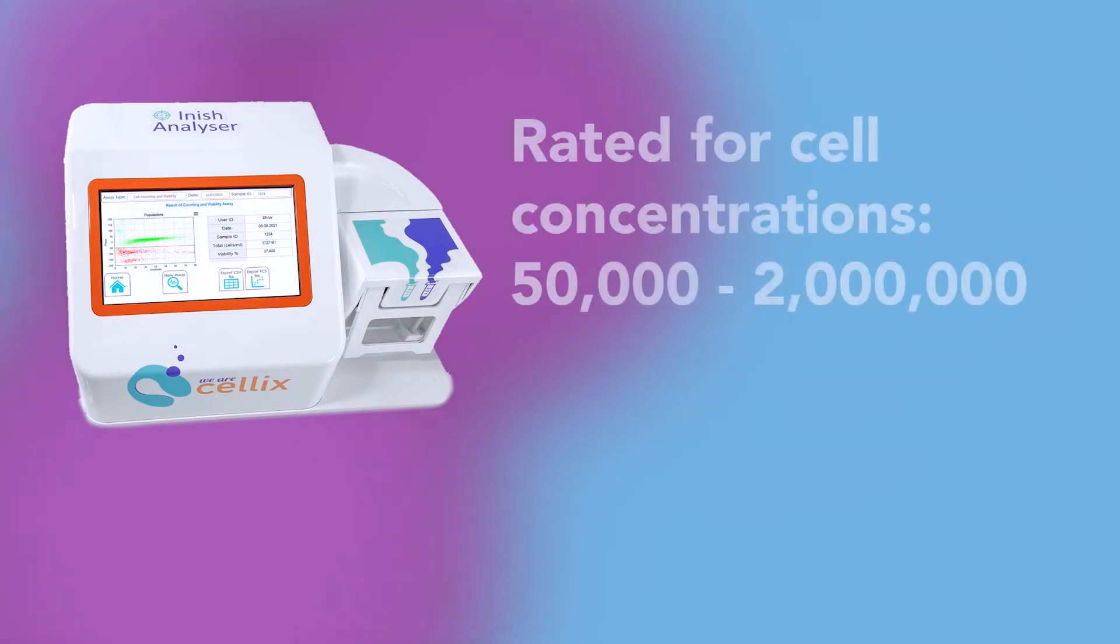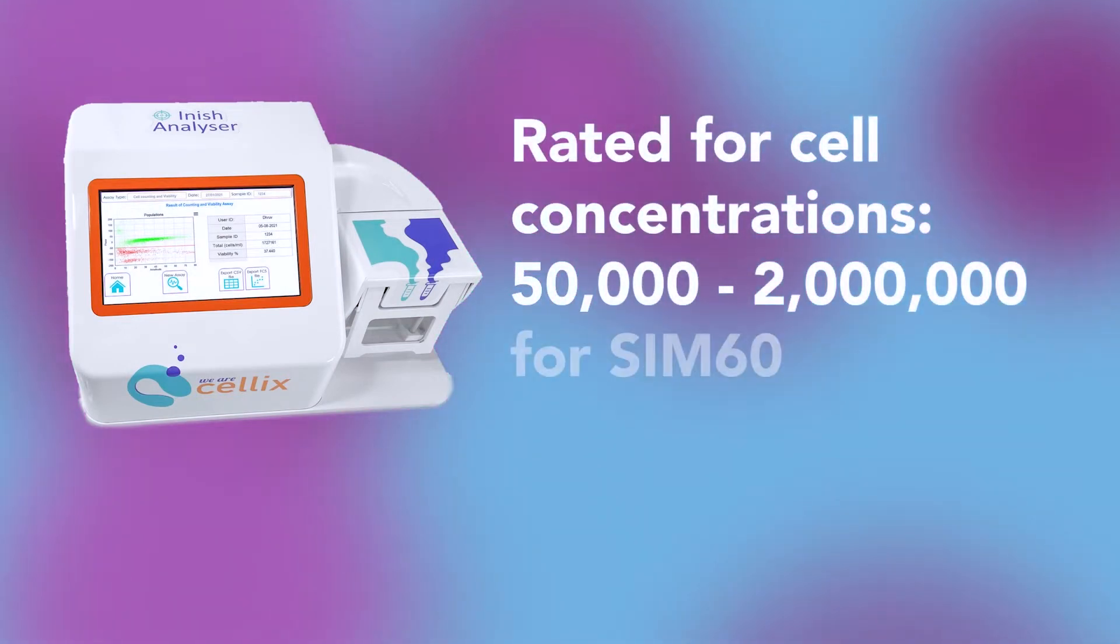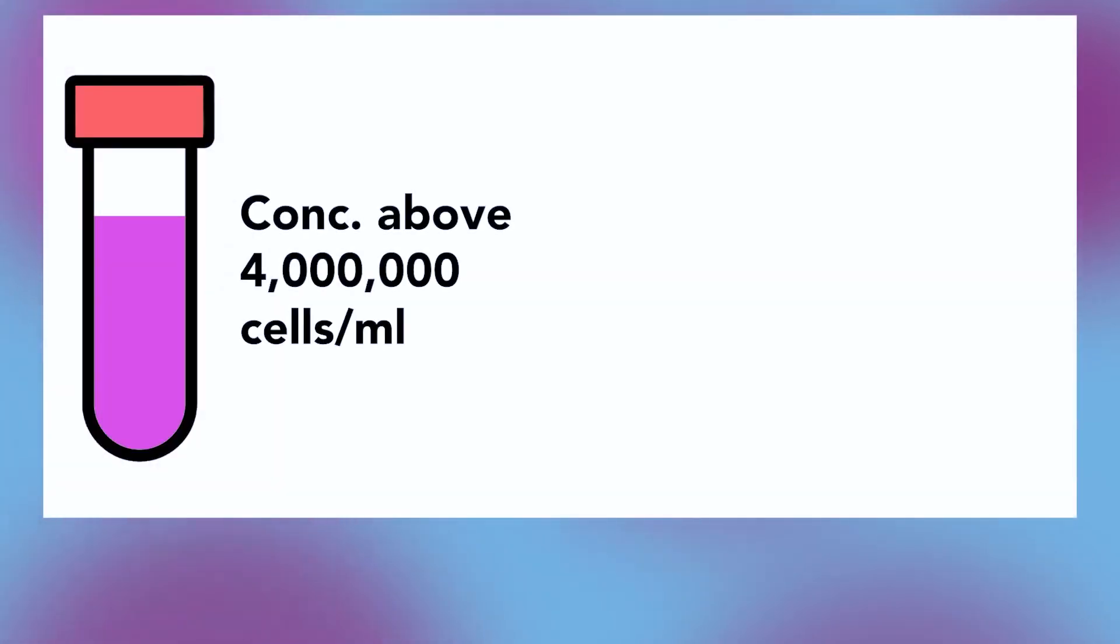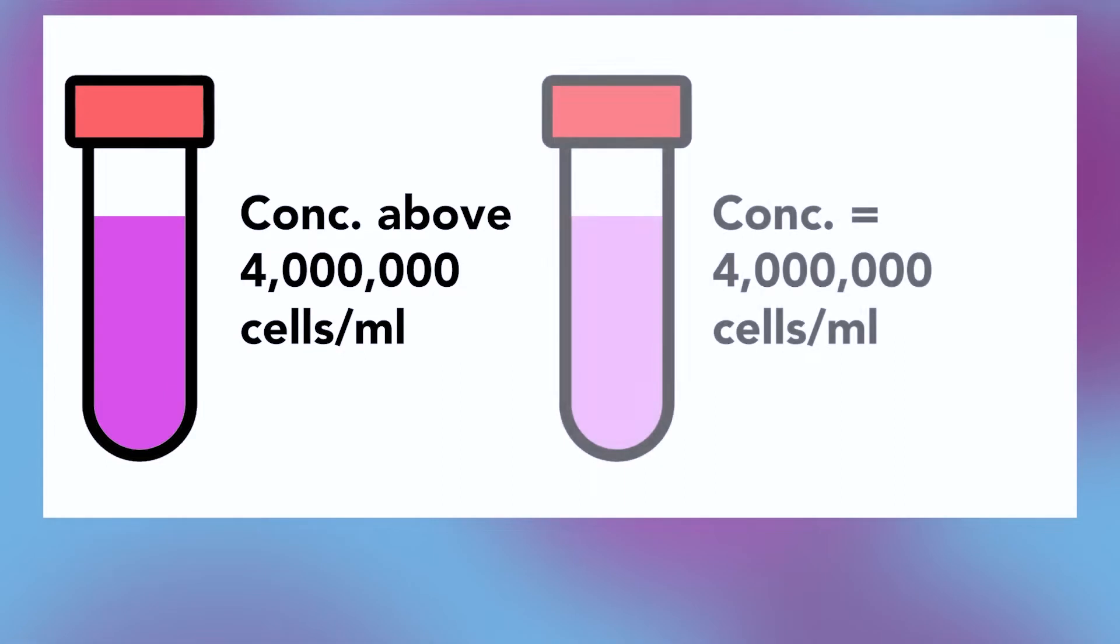The Inish analyzer is rated for cell concentrations between 50,000 and 2 million cells per milliliter for Sim60, so if your sample concentration is above 4 million cells per milliliter, dilute it down to 4 million cells per milliliter.